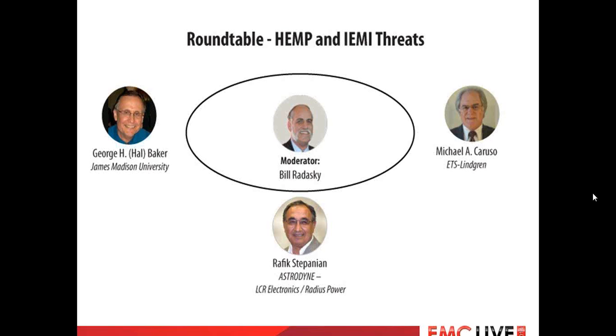But the point is, as George mentioned, the big difference is the fast rising pulses for EMP and IEMI, which are really quite different. So in most cases, lightning protectors will reduce the transients somewhat and can therefore be useful. But the best idea for protecting from HEMP and IEMI is to use protectors actually designed for the expected waveforms. George, did you want to add anything more to that?